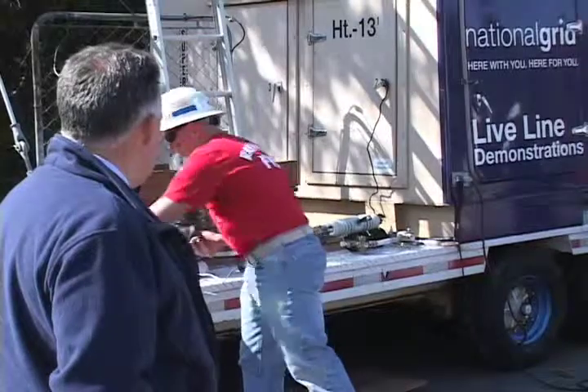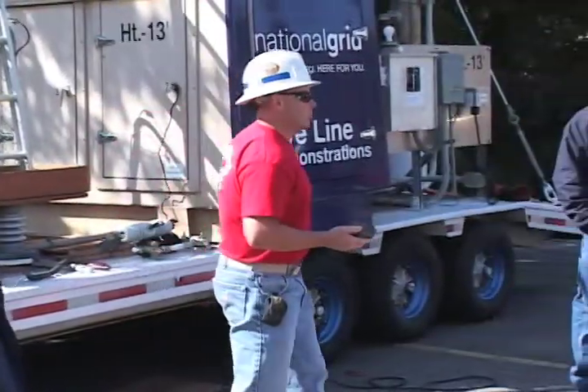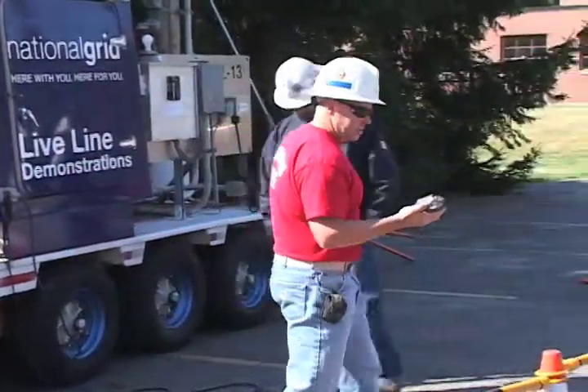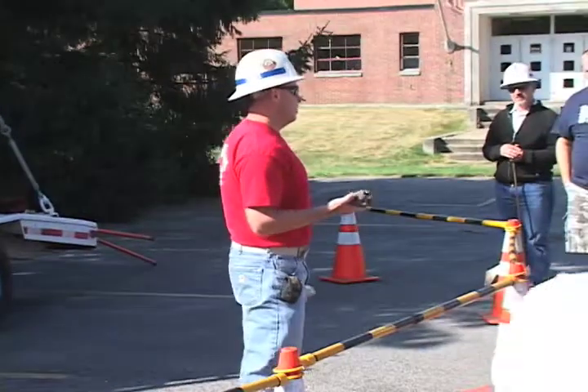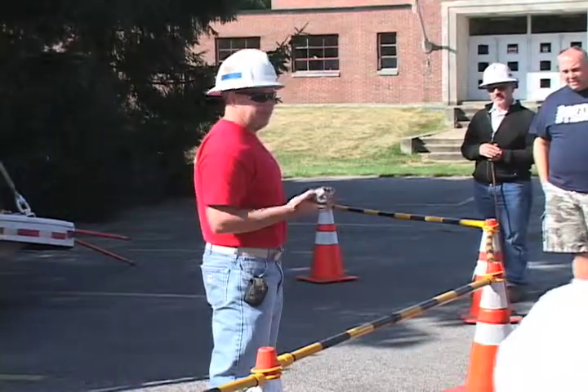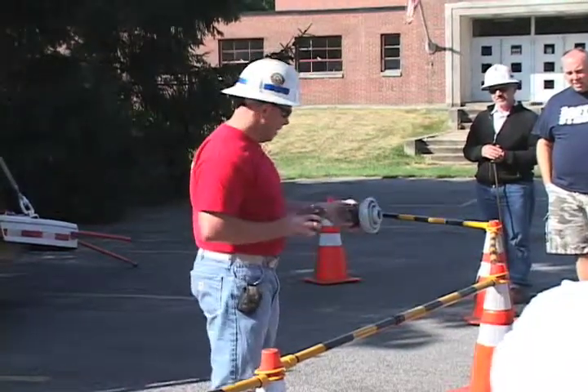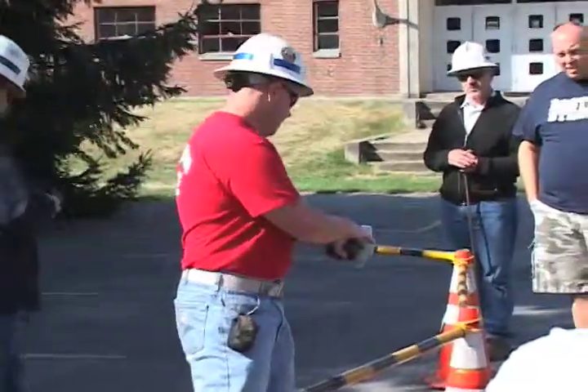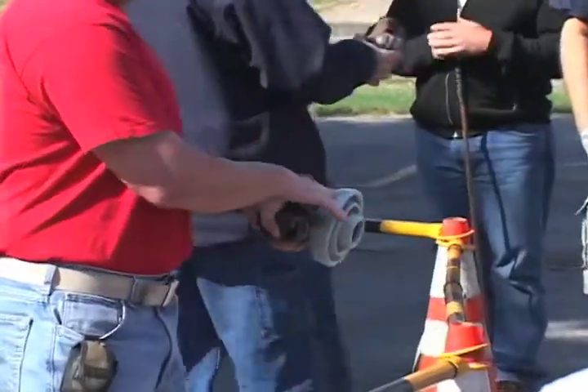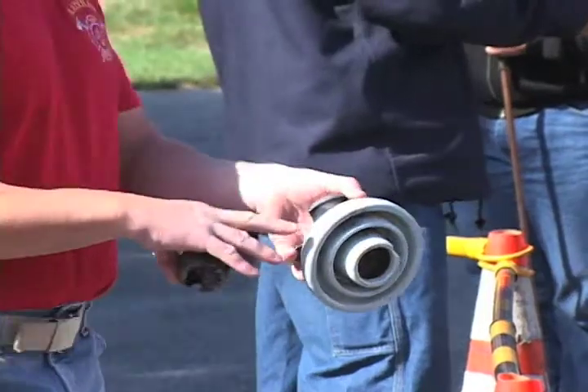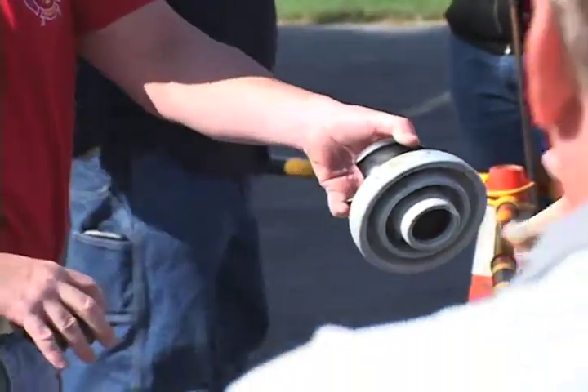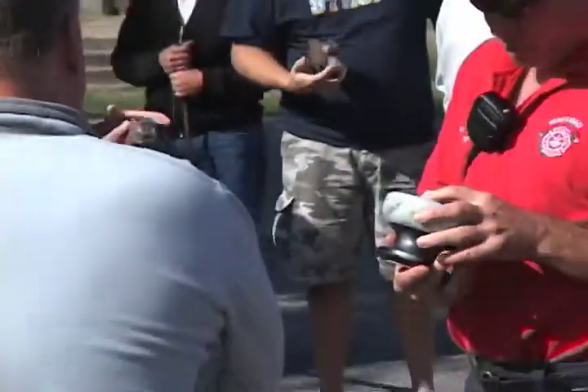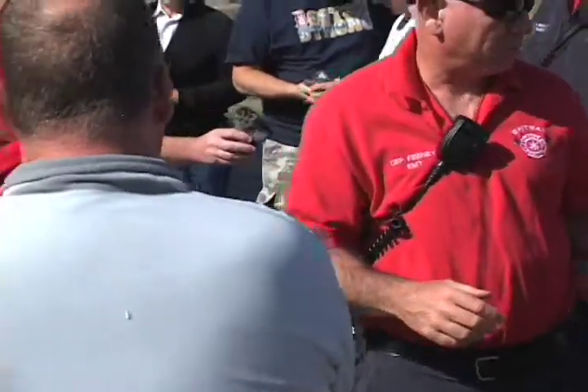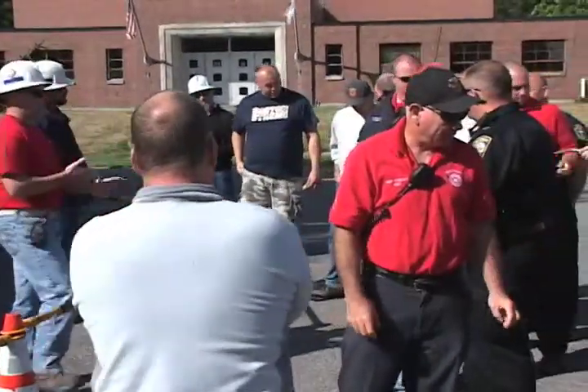I've been doing this for the past year, so I did a little bit of research on an arc flash. An arc flash can produce temperatures up to 34,000 degrees in 1/110th of a second. I just have to prove this was a call in Stoughton. Had a squirrel get between the conductor and the ground and it actually melted the copper and infused it into the porcelain. And then this was a phase that came down in a gravel pit and just burned, turned the gravel to glass.